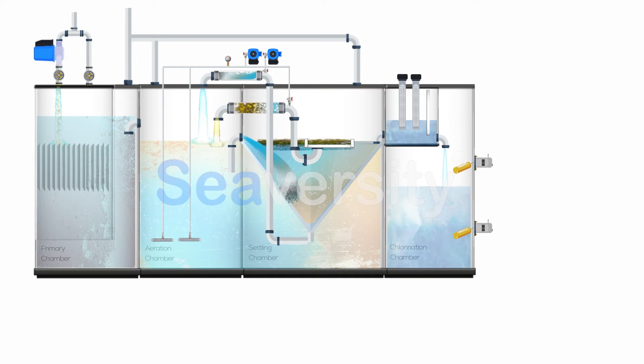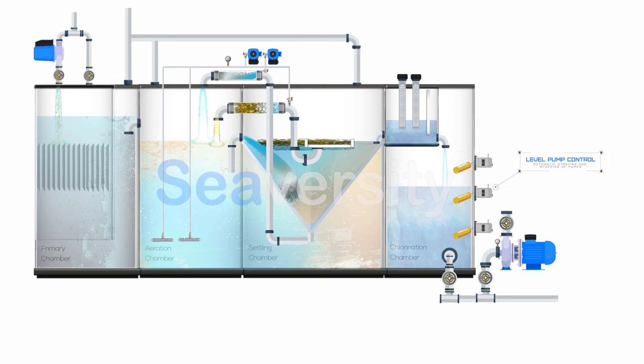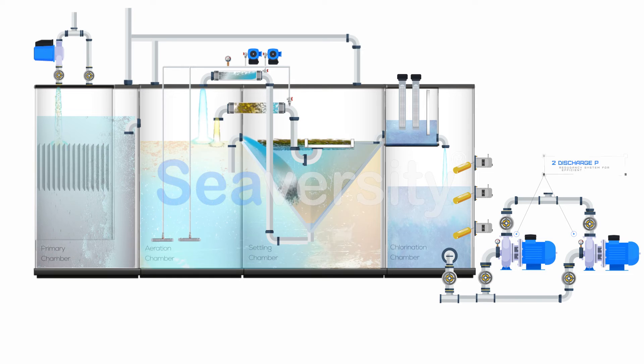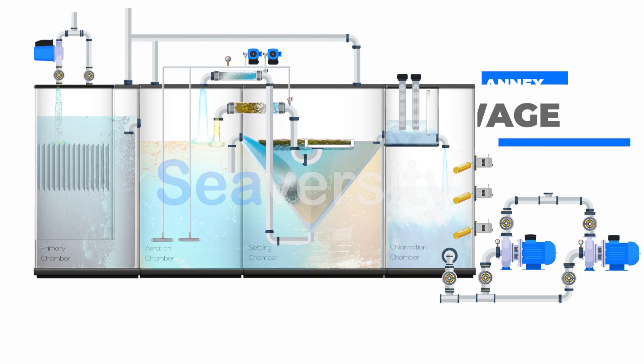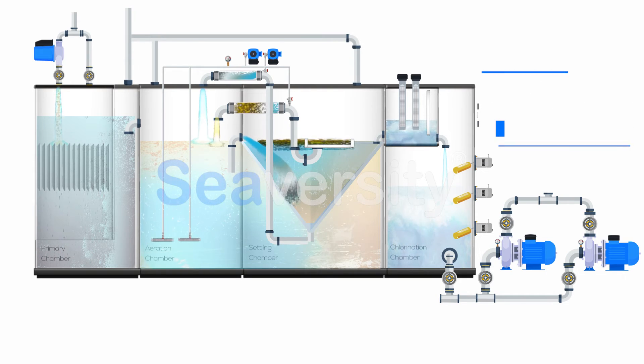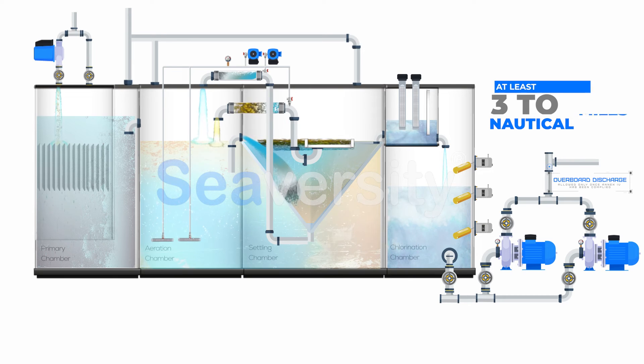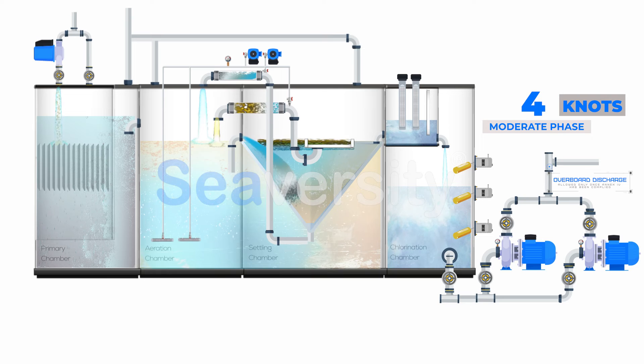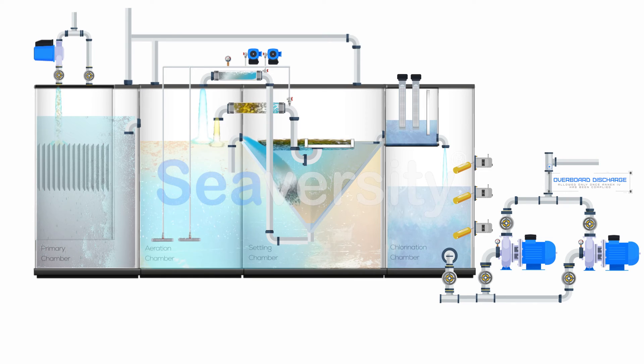Connected to this system, there's a level switch connected to the discharge pump that automatically sets the pump to start and stop based on the water level in the tank. There is also a redundancy standby pump in case the other pump requires maintenance. Discharging the treated water takes a carefully controlled process. There are strict rules outlined in Annex 4 of the sewage discharge criteria that set where, when, and how to discharge sewage. Generally, the vessel needs to be at least 3 to 12 nautical miles from the nearest shore and moving at a moderate pace of around 4 knots, to ensure the treated effluent disperses properly without harming marine life or water quality. When discharge isn't possible or practical, the effluent can be stored in the sewage holding tank and discharged on a later schedule.